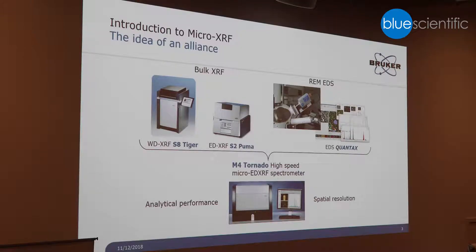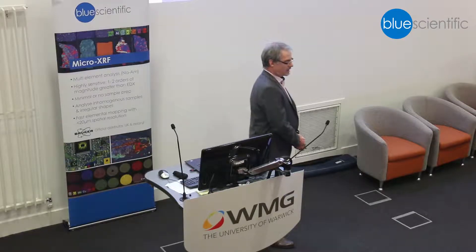The idea behind Micro XRF: on one side you deal with Bulk XRF, which is a standard method for elemental analysis, and you can go down to the single PPM range. On the other hand, Bulk XRF doesn't give you the spatial resolution or the information about at which location you can find which element.